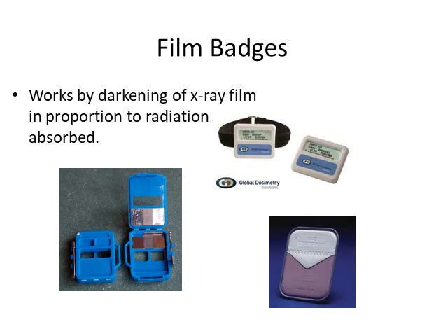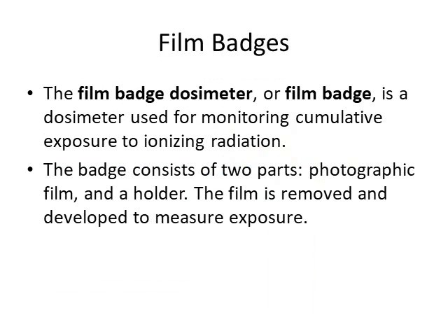Film badge dosimeters are the most commonly used personal monitors compared to TLD and OSL dosimeters, because they are very low cost compared to other dosimeters, and they give a permanent exposure record. It works simply by darkening of X-ray film. It is nothing but a very small X-ray film placed inside a plastic container.